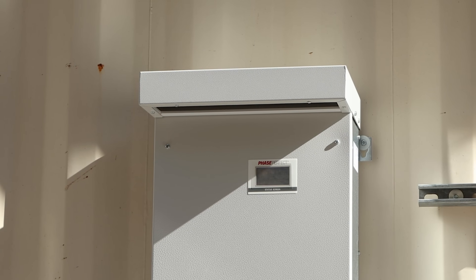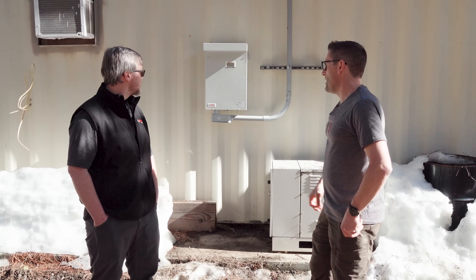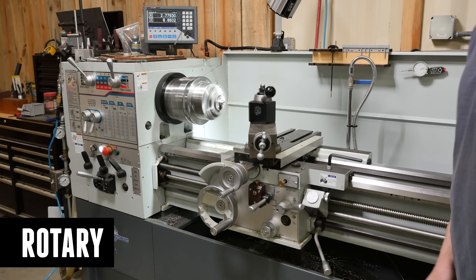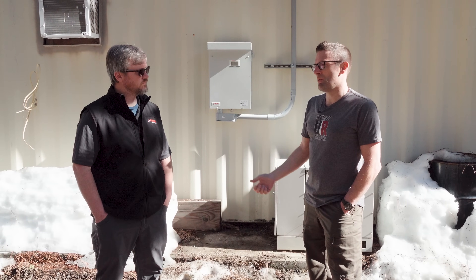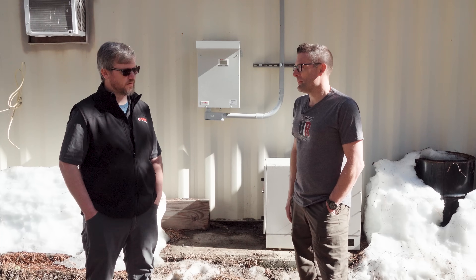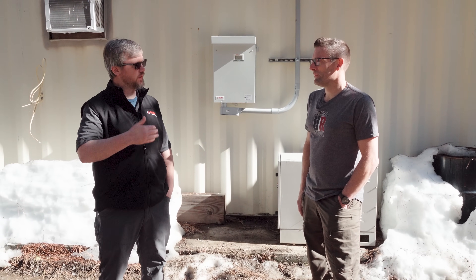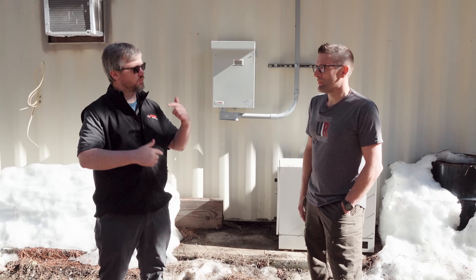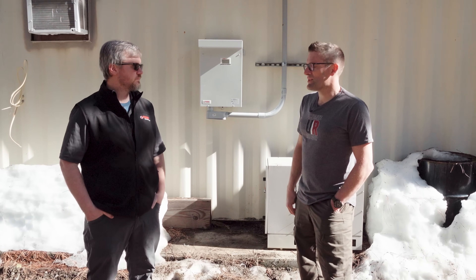I really like the idea of having something tight up against the building. We installed the rain hood so we're kind of all-weather certified, which is nice. I did have some startup motor lagging with the big lathe — it's got a 75-pound chuck on it, and when you're going up to full speed it just takes a while. That adds wear and tear to the electrical motors. With those big high-inertial loads like your lathe, you really need the voltages between the three phases to be balanced to help all three windings of the motor pull together.